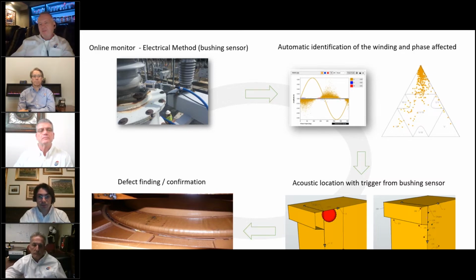Excellent. So you had really 3 modes of measurement here that brought it round: the gas analysis initially, then the acoustic, and the online PD monitoring as well. Correct, all 3 mechanisms came back. Now, is there a portable monitoring solution they could put on the transformers rather than doing it fully? Sometimes people don't want to go to the expense of doing every transformer, so are there portable units they can use?